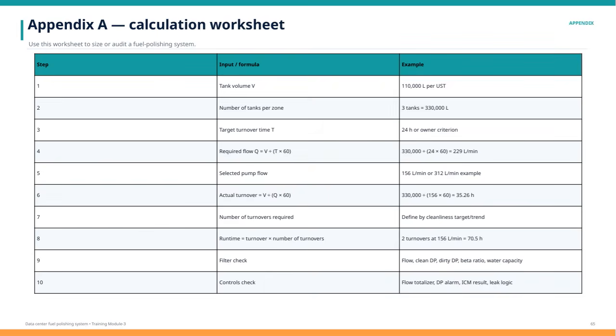The target turnover time, or how frequently the total volume needs to be processed, is typically 24 hours, or it could be based on the owner's criteria. Using this, we calculate the required flow rate, Q, which is the volume divided by the product of turnover time and minutes per hour. In the example, this results in 229 liters per minute. Then, we compare this with the selected pump flow rate, which might be 156 or 312 liters per minute.